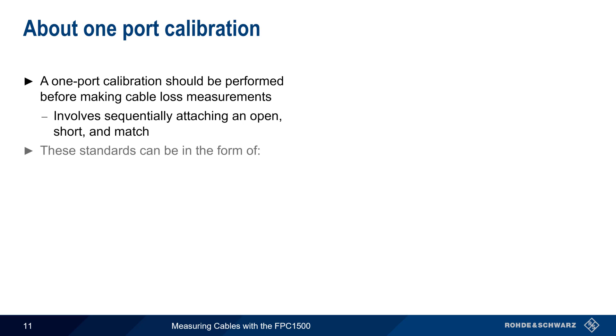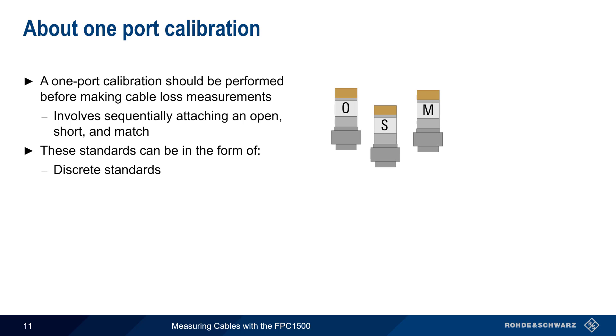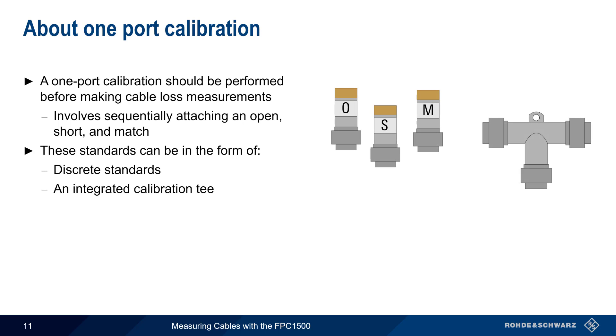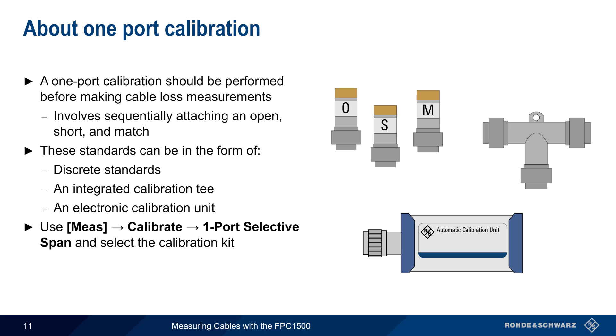Before making any one-port measurements, a one-port calibration should be performed. This process involves sequentially attaching an open, a short, and a match or load to the location where the cable under test will be connected. These standards can be in the form of discrete standards or may be combined into a calibration T. In addition to these manually switched standards, electronic calibration units can also be used. These switch their internal standards in and out automatically and are controlled by the FPC. Regardless of which type of standards are used, the process is started by pressing the Measure hard key, pressing Calibrate and One-Port Selective Span, and then selecting the calibration kit. Then simply follow the prompts to run the calibration process.